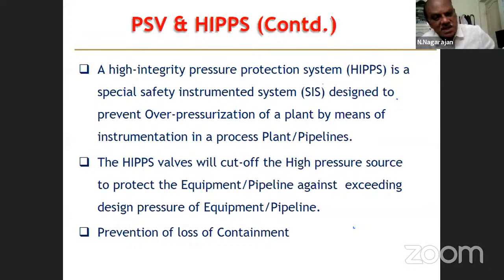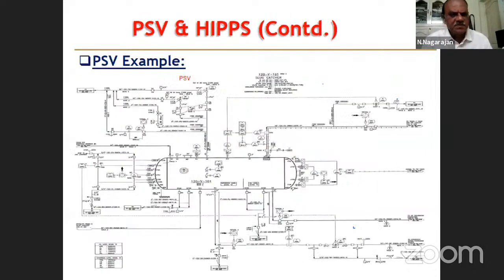So how do we prevent that? We put a pressure protection system. High integrity pressure protection system is nothing but a set of valves. Two valves, they are specially designed valves, very costly valves, and they will close. In the event they measure the pressure beyond a set point, they will immediately close and isolate the total plant. This is called the HIP system. And this doesn't lead to any loss of containment because it stops the input itself.